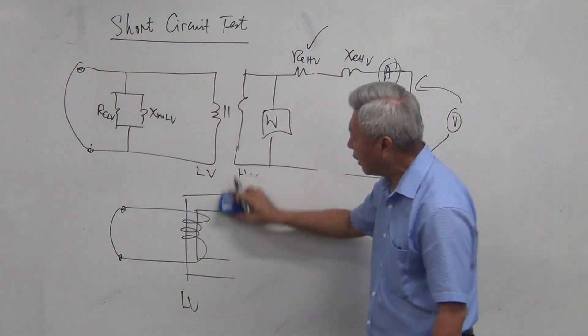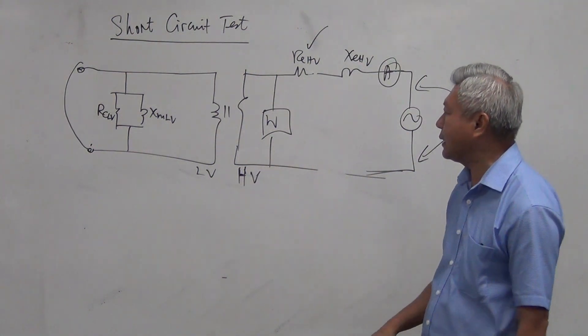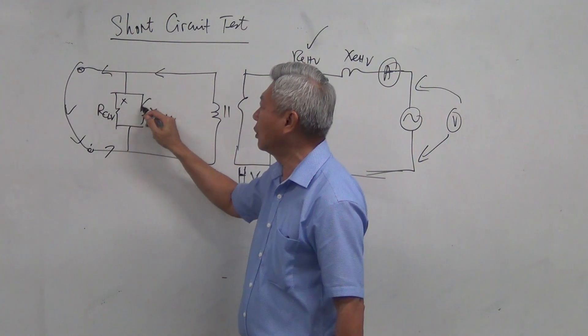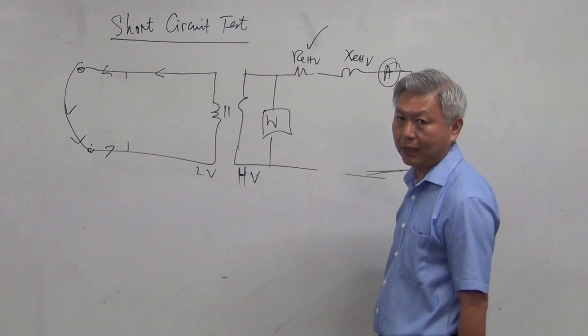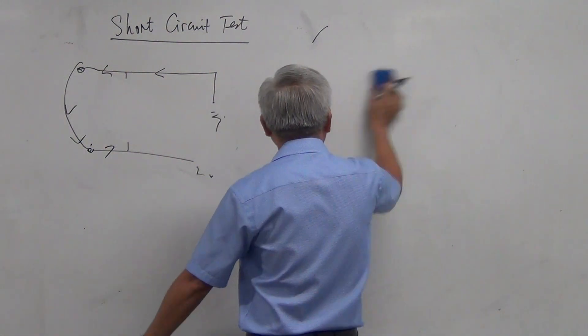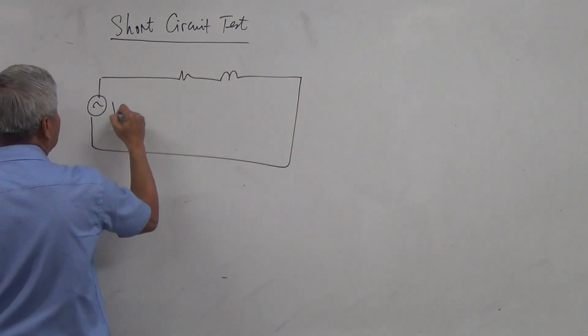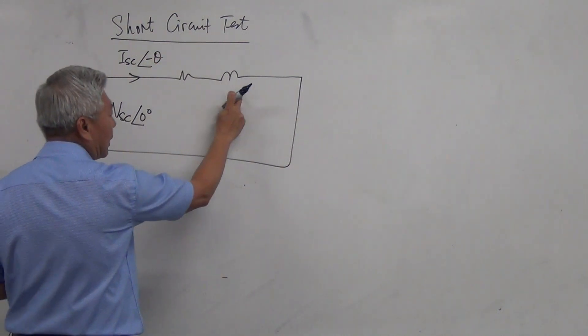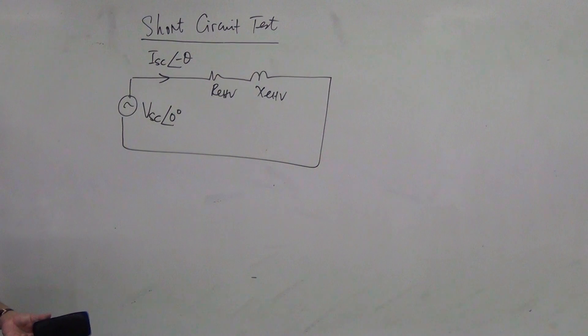What is the equivalent circuit for the short circuit test? If you recall from basic DC electricity, current chooses to go through the short circuit path and not through anything that has impedance. So in other words, those two parallel branches disappear — they have been short-circuited or bypassed. Our short circuit test equivalent circuit is just a pure series circuit with a power supply, REHV and XEHV.